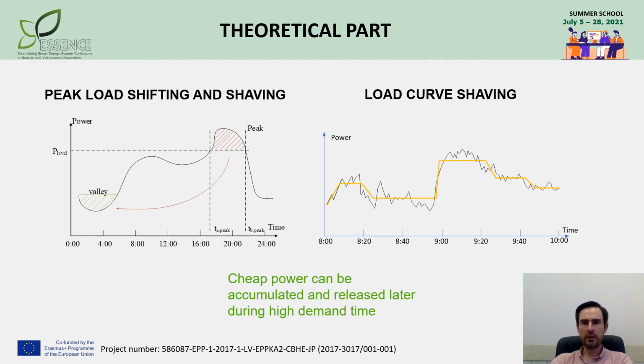Let's discuss what peak shifting is based on the picture on the slide. It seems that the demand varies a lot during the day. The peak demand happens around 7 p.m. and may last about 2 hours. But in the morning before 8 a.m. the load is very low.